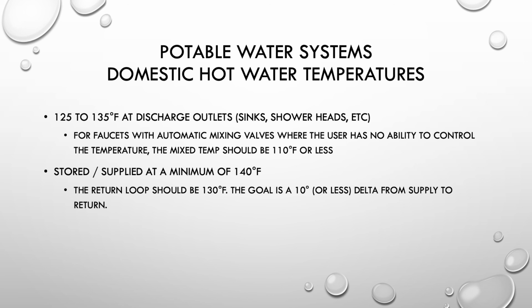I included this slide as a reminder of some requirements for our potable water system and domestic hot water temperatures. Just a reminder to be safe with our new parameters, increasing the temperature here on campus. We request 125 to 135 degrees Fahrenheit at the outlets, such as sinks and shower heads. Automatic mixing valves should have a mixed temperature of 110 degrees or less, since the user can't control that temperature. Storage or supply temperature should be a minimum of 140 degrees Fahrenheit, with the return around 130 degrees. Our goal is a delta of 10 degrees or less between supply and return.